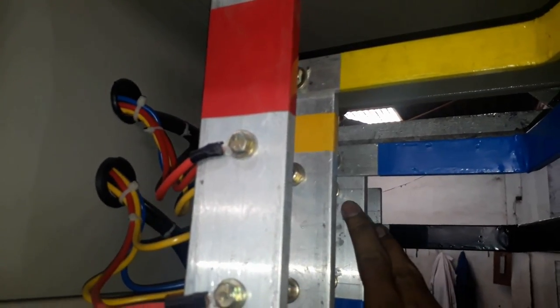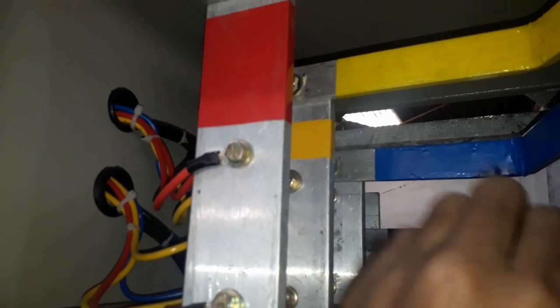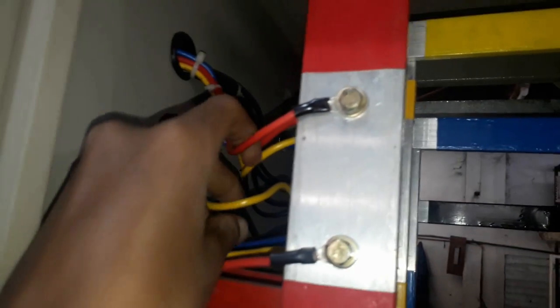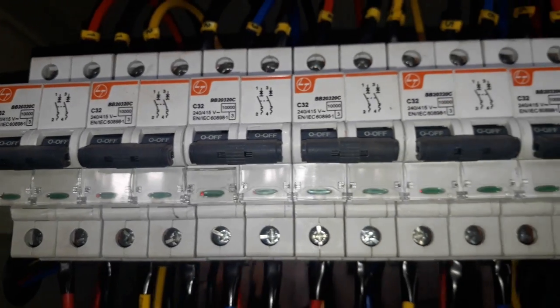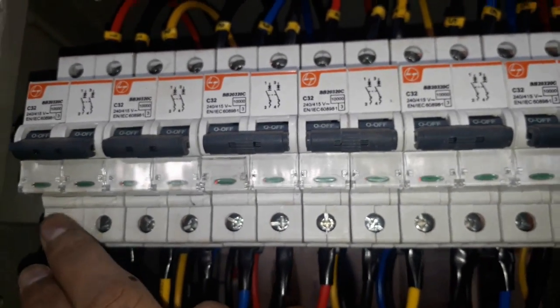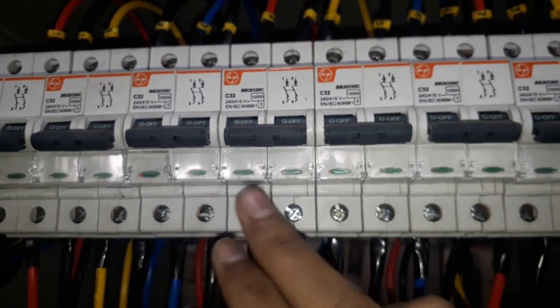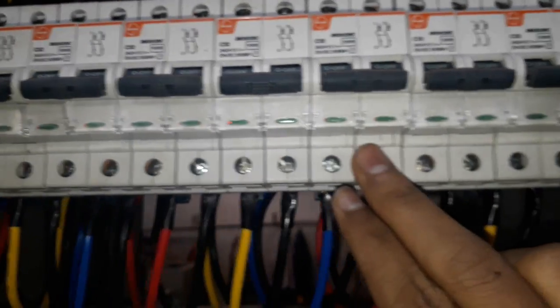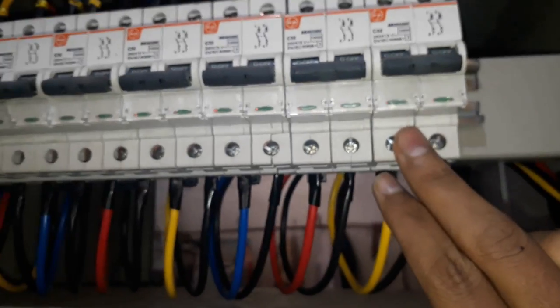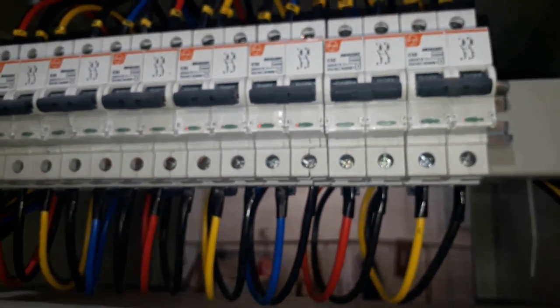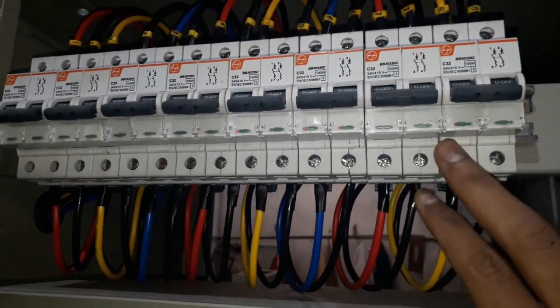Here you can see this is the bus bar chamber at the center of the panel, and there are four bus bars here: R, Y, B and neutral. We are taking cables from these bus bars and giving supply power to the phase in of the circuit breakers. These are 32 ampere, 2 pole circuit breakers, 8 in quantity, and from the phase out of these circuit breakers we are connecting to terminal blocks.